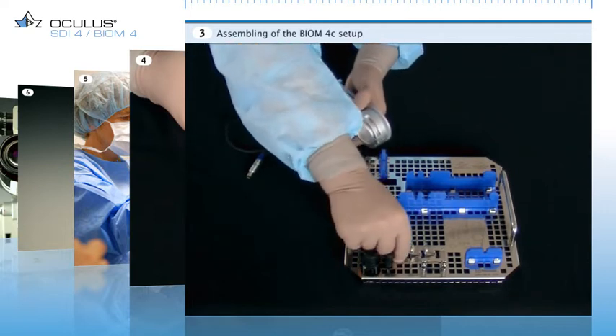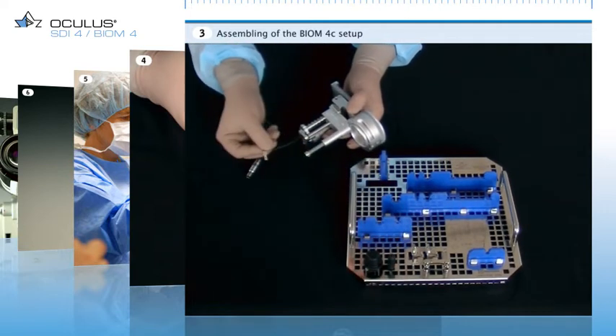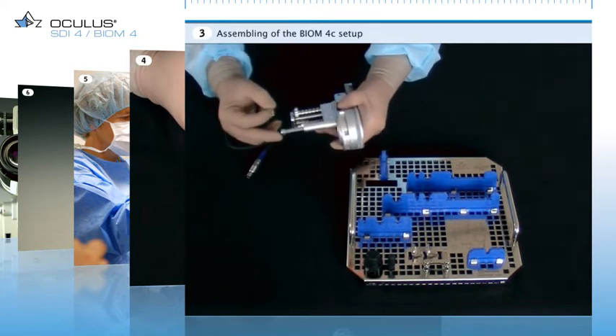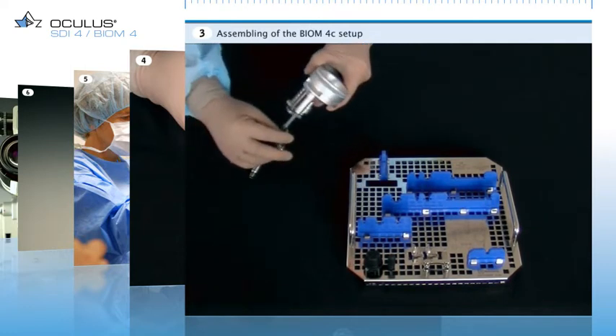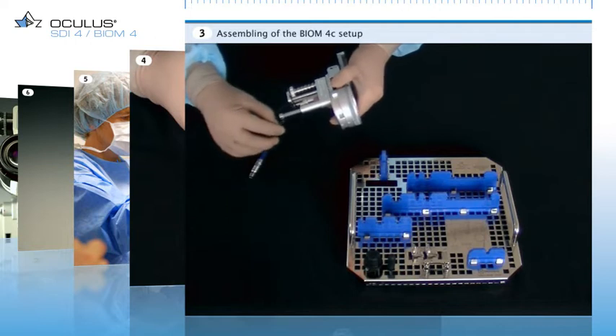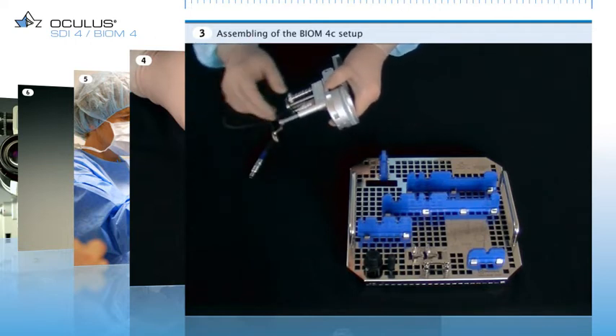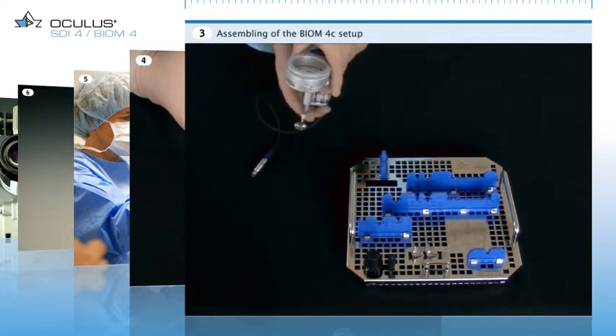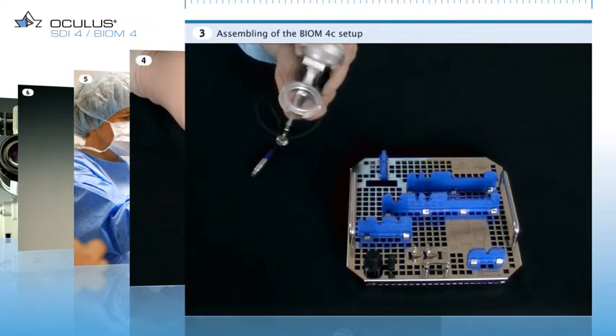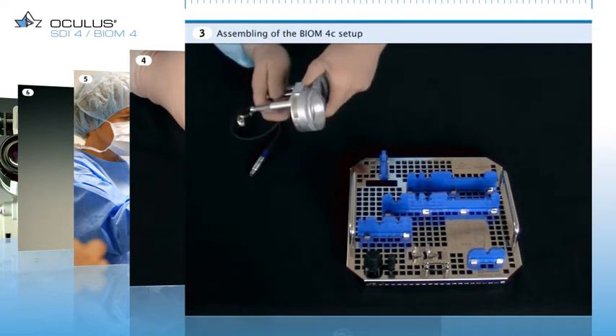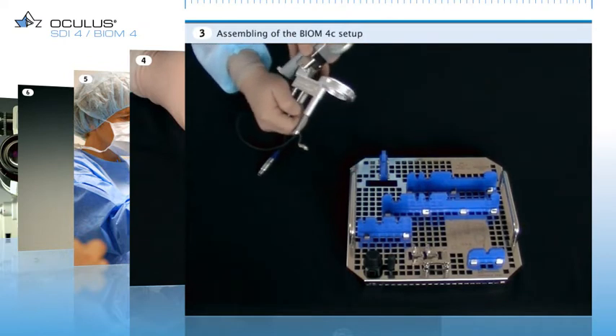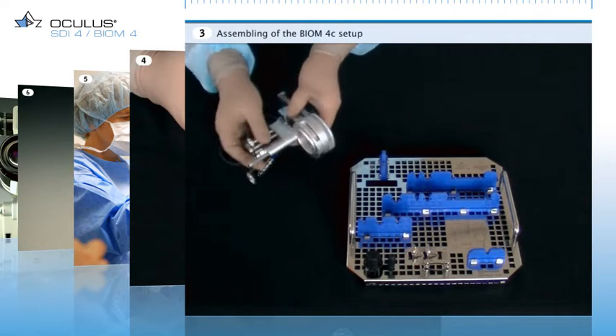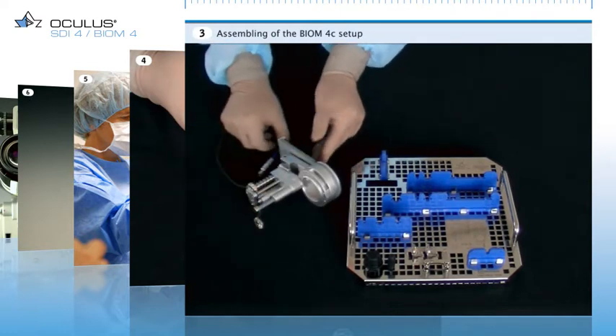Take an appropriate front lens and insert it into the lens holder at the bottom end of the BIOM. Now the BIOM is fully assembled and ready for use. A safety check must be performed before every use. This includes checking that the lens holder runs smoothly. Then swing out the adapter by 90 degrees. Also check its return travel.